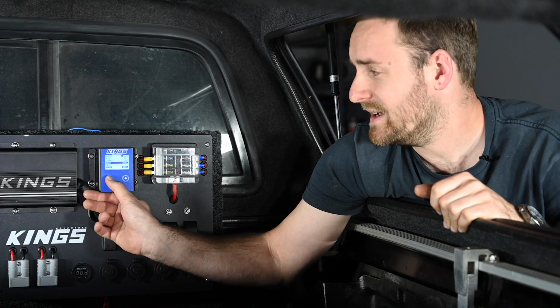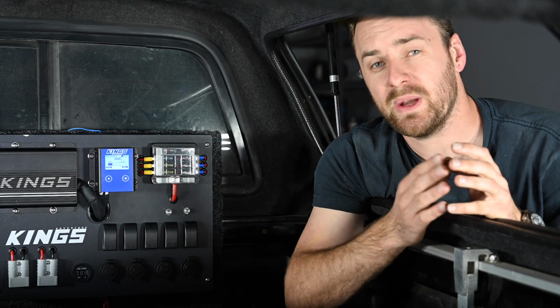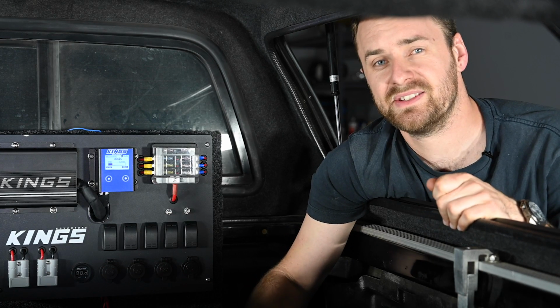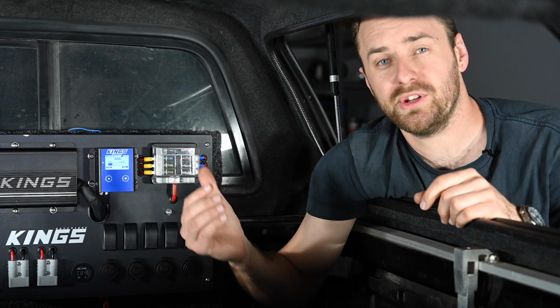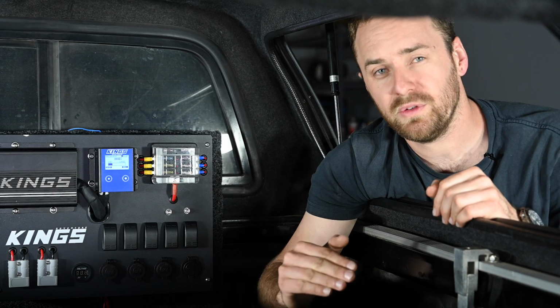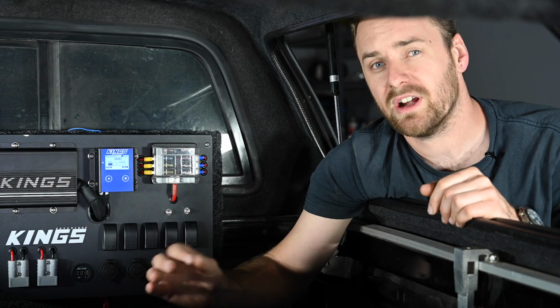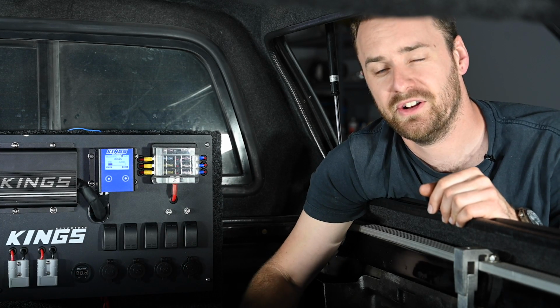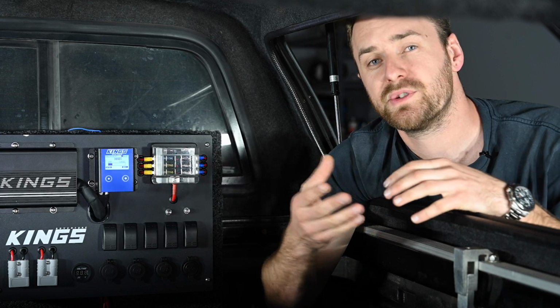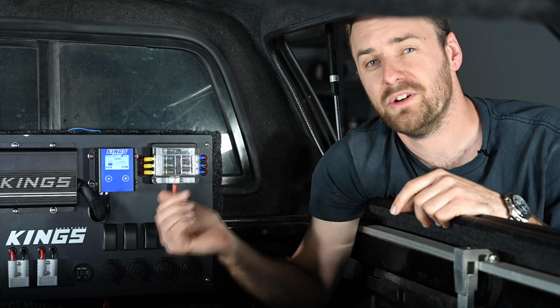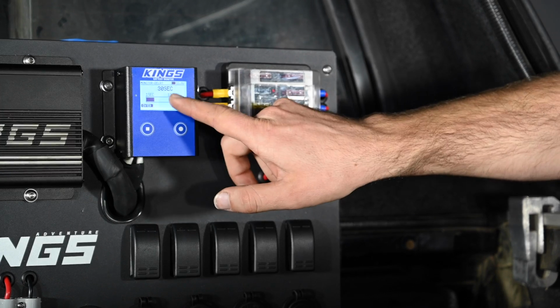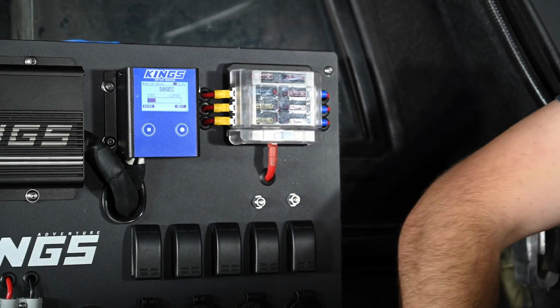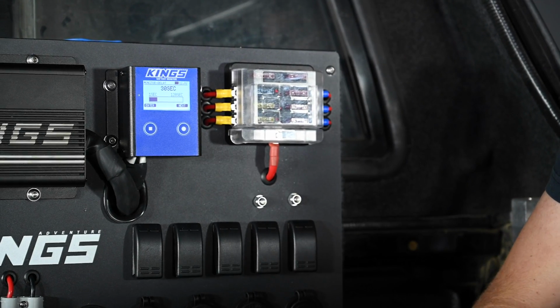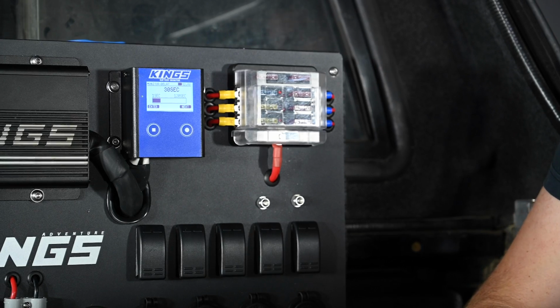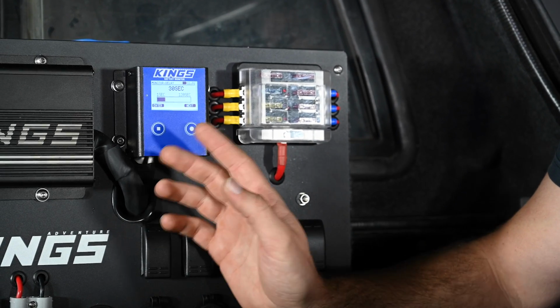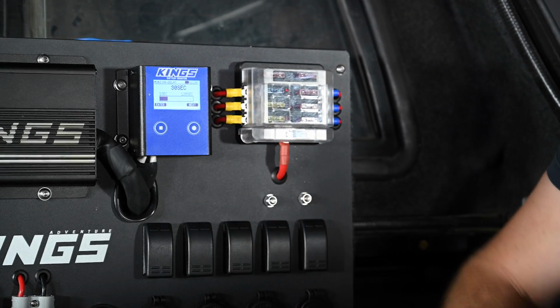Next is delay. Now delay can be set between 1 and 120 seconds, and that's the length of time that your unit needs to sense a low voltage, high voltage, or overcurrent situation to actually turn it off. So that means if you've got a momentary voltage spike or dip, it's not going to turn your system off. The default is 30 seconds, which means it'll take 30 seconds of an over voltage, under voltage, or overcurrent situation for it to turn off, and then 30 seconds for it to attempt to reconnect.